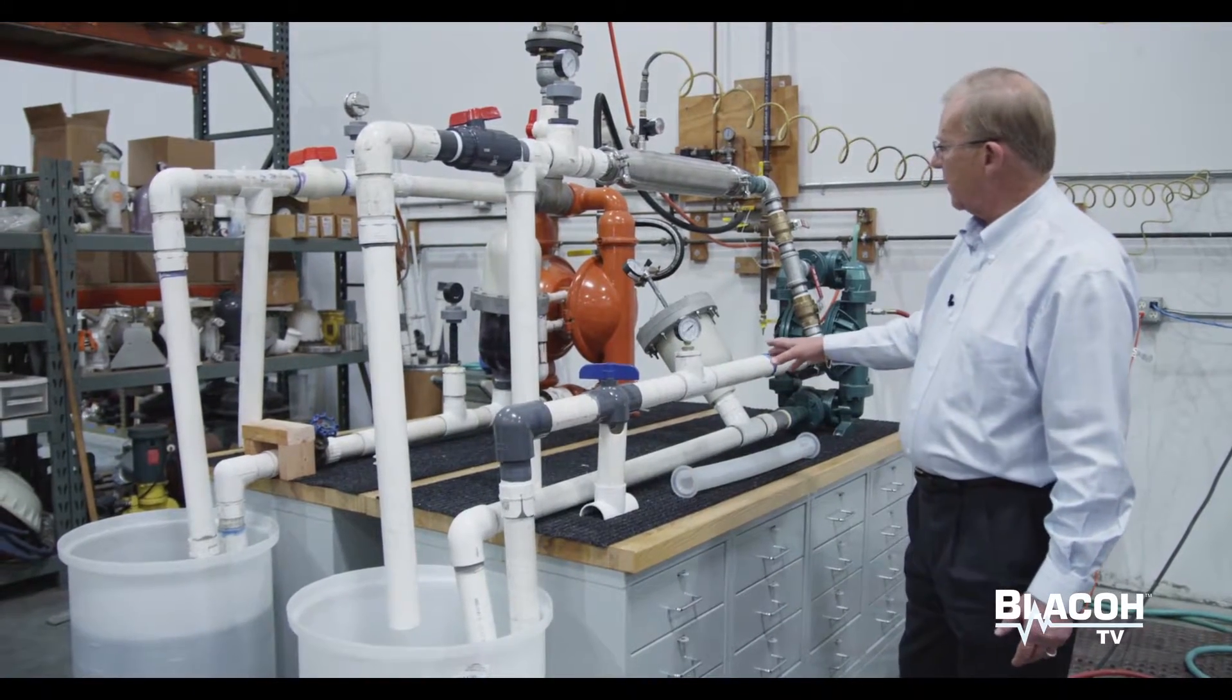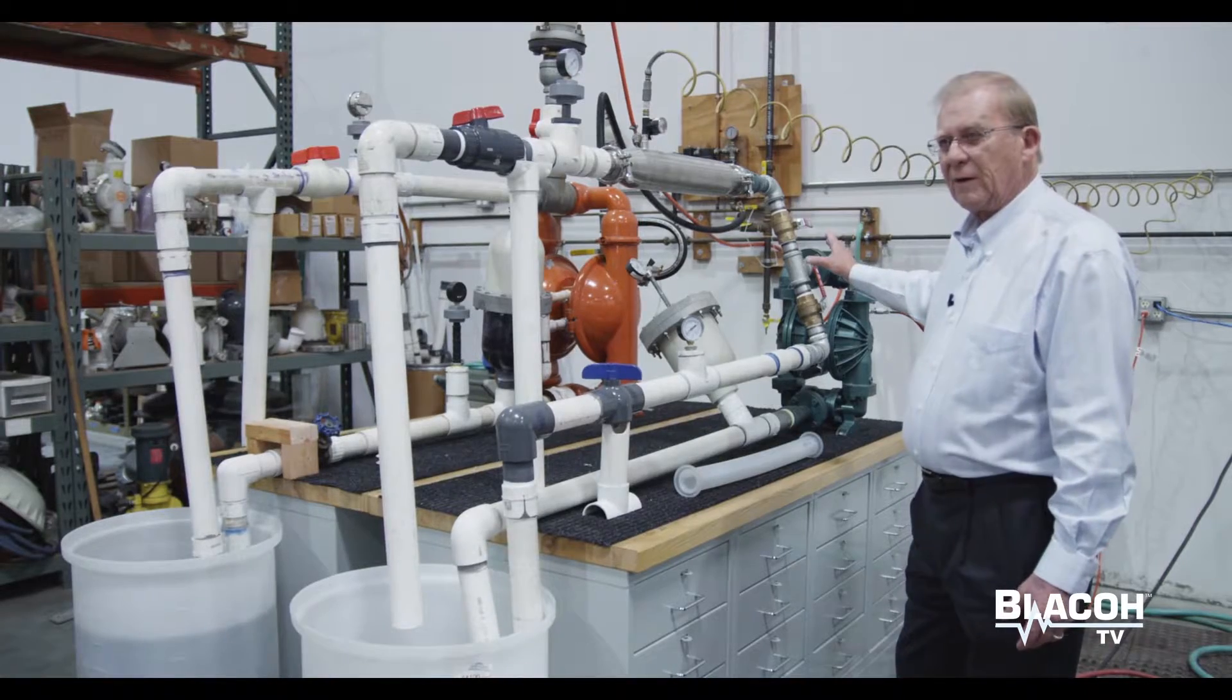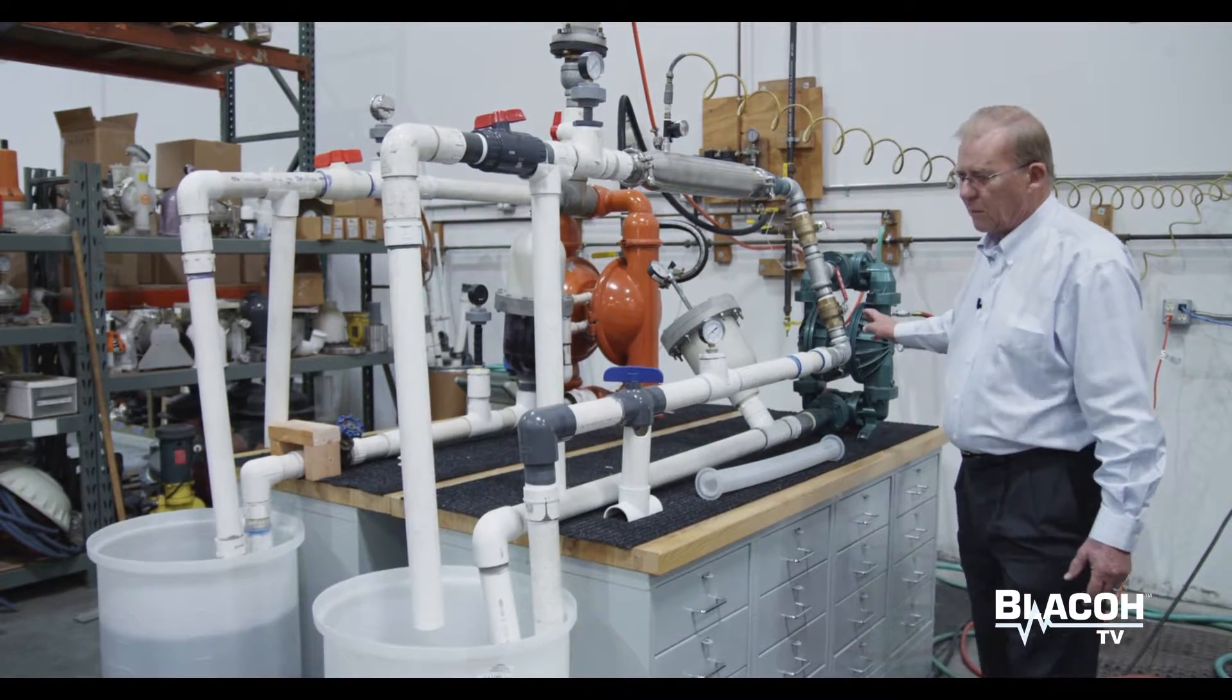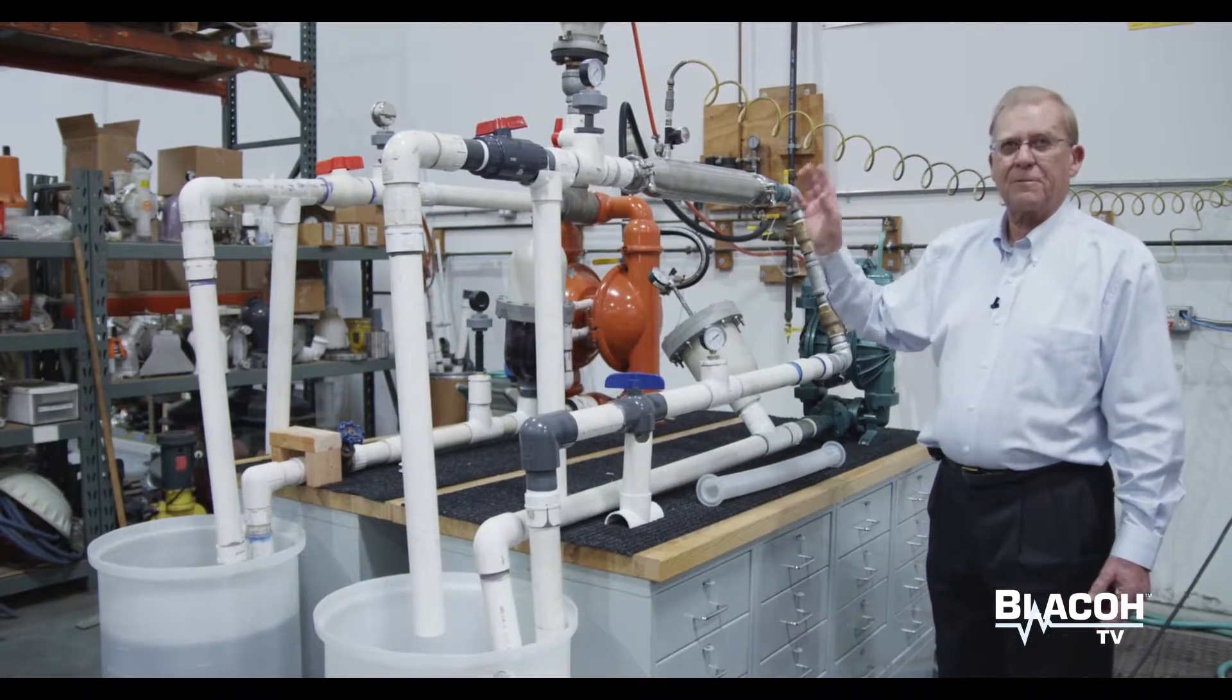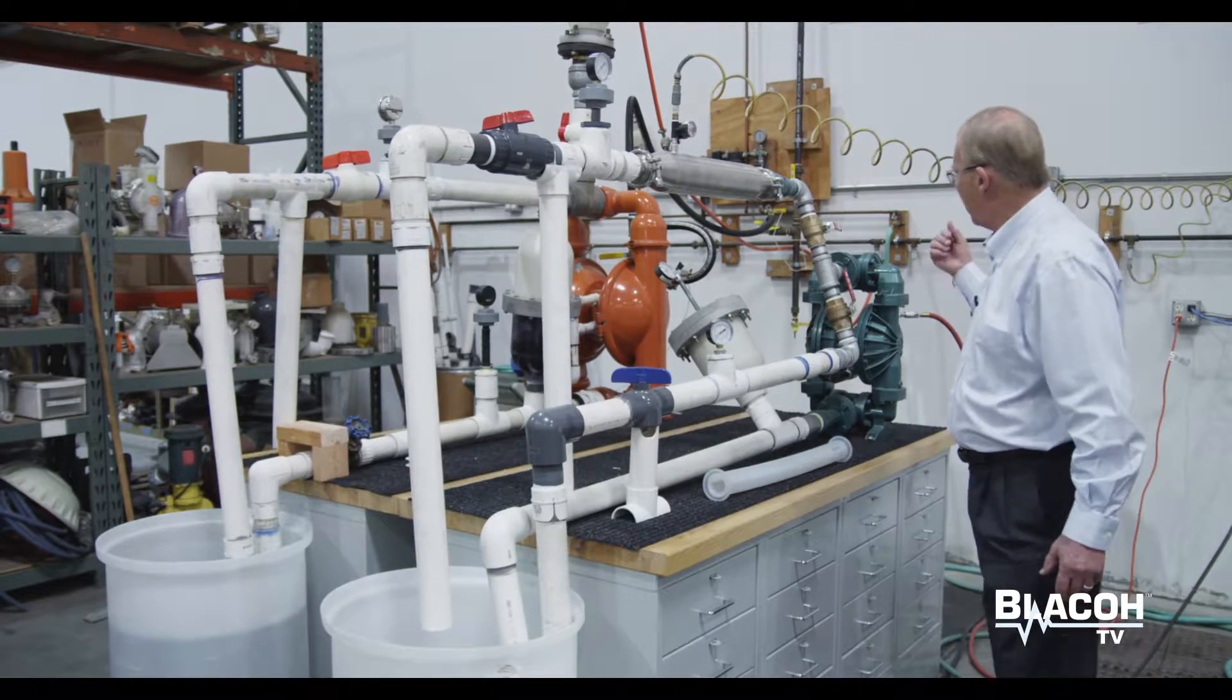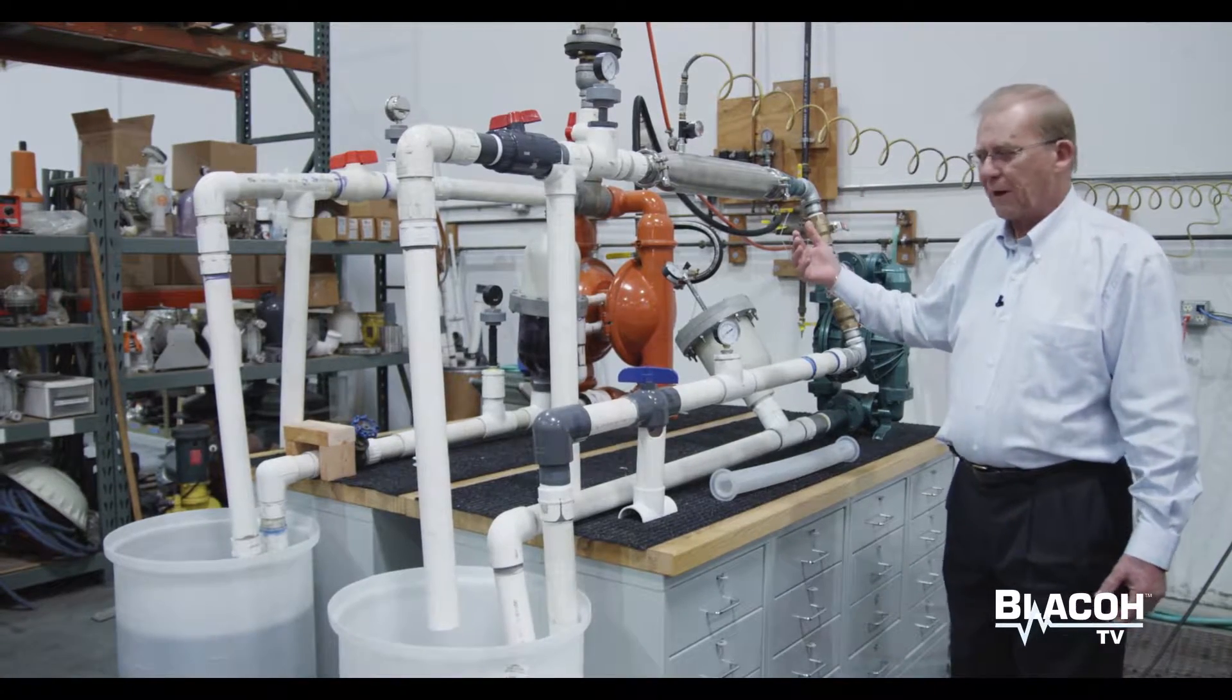So this is without the dampener. You're going to see some mechanical vibration from the pump. There are basically two types of vibration created when a pump is running, especially an air diaphragm pump. One is the hydraulic vibration created by the stop start, the flow of liquid, but the other is a mechanical vibration created by the pump shifting its diaphragms back and forth, balls and seats raising and lowering.